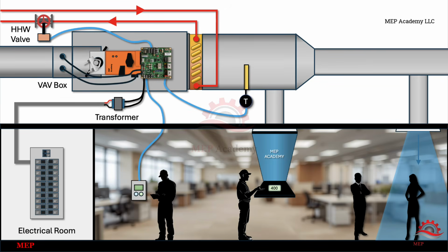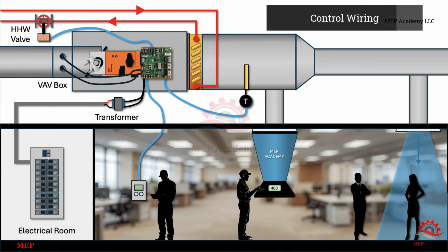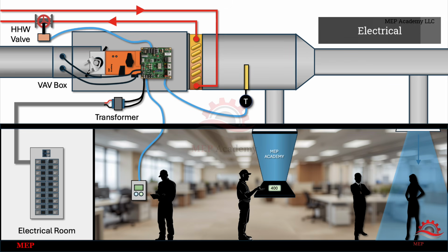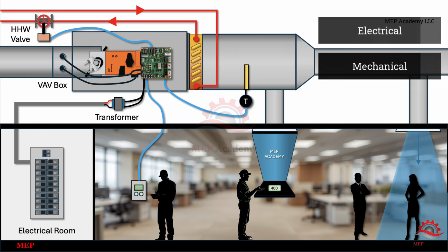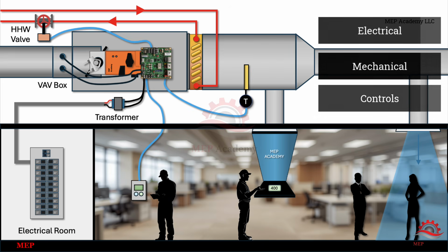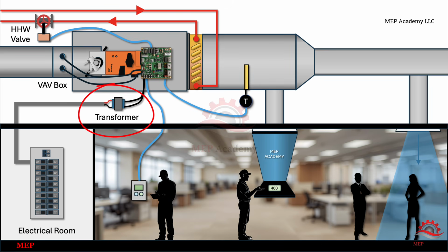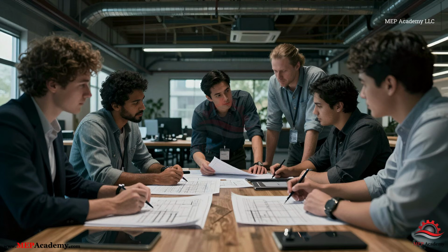The fourth coordination issue involves control wiring and building automation system interfaces. Modern HVAC systems rely heavily on controls, interlocks, and communication between equipment. Electrical contractors typically provide power wiring, while mechanical contractors provide equipment, and a controls or building automation contractor provides system logic. The boundary between these scopes is often unclear in contract documents. Typical conflicts include who provides control transformers, who installs control conduits, and who pulls interlock wiring between systems such as VFDs, safeties, and shutdown signals. Because equipment may power up successfully without these connections completed, the problem often does not appear until startup or commissioning. When control responsibilities are not clearly defined, multiple trades may need to return to complete work that was assumed to be included by others. Clear scope definition during estimating prevents these late-stage coordination problems.